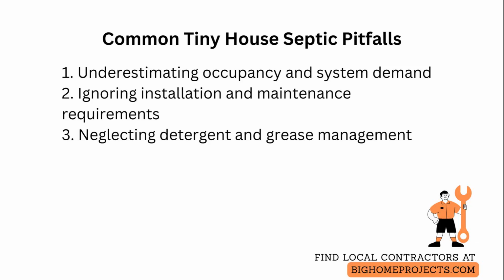A third concern is ignoring detergent and grease management, which accelerates biomat and can clog soil absorption fields. The remedy is using low-phosphate detergents, avoiding grease-down drains, and diverting high-sodium or non-biodegradable wastes away from the septic system.